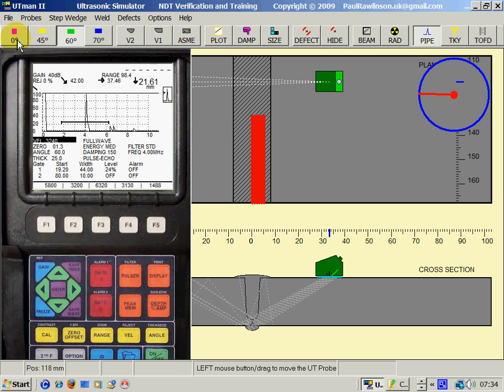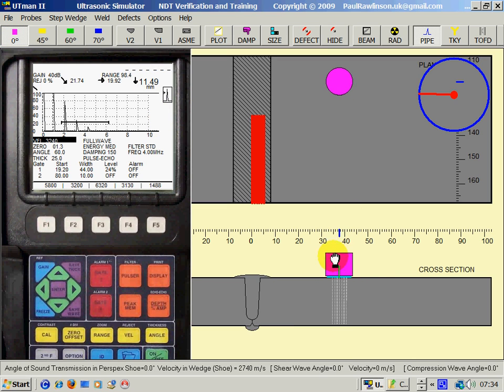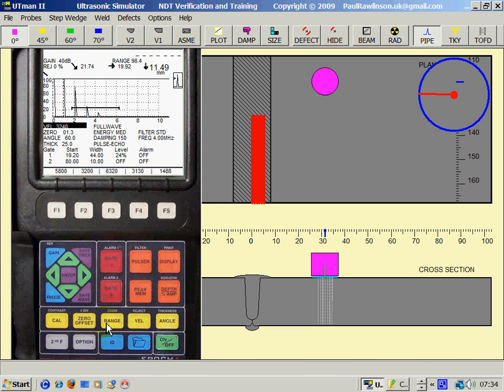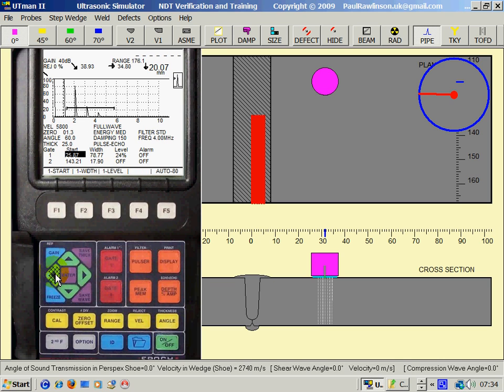Now to calibrate for the 0, again we'd have to change the velocity. Click on velocity. The velocity of compression wave is approximately 5,800 meters per second in steel, carbon steel. And move the gate position this way to catch the first echo. Change the angle to 0.